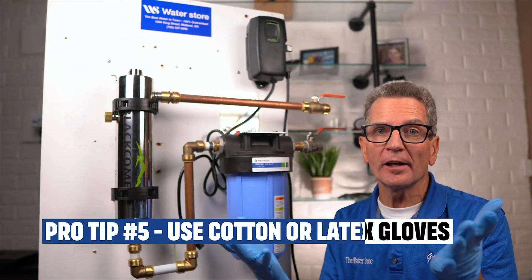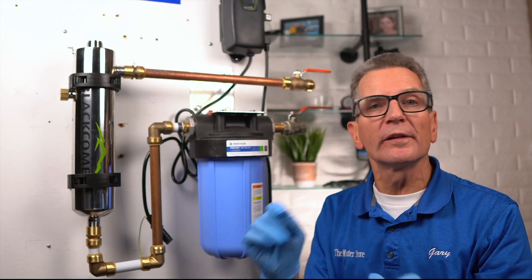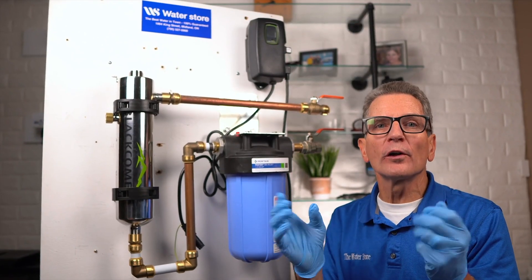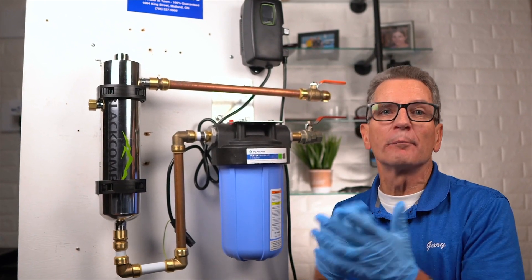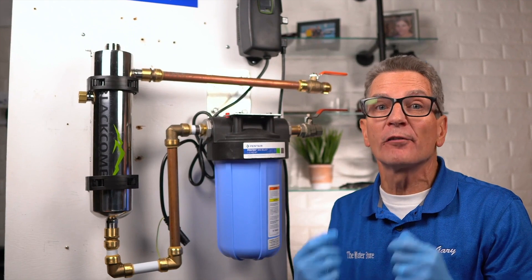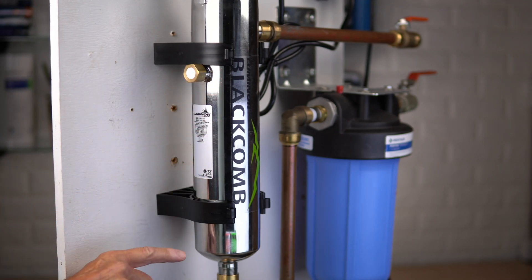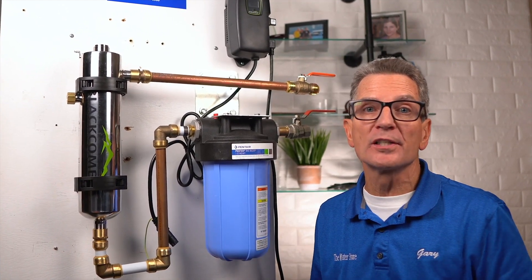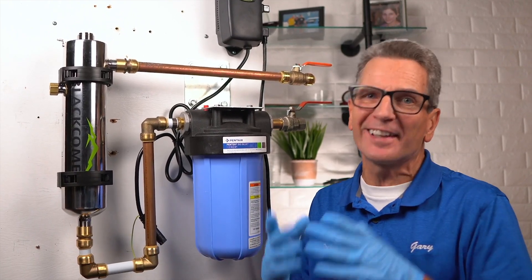Pro tip number five: the use of cotton or latex gloves is definitely recommended whenever you're handling anything to do with the quartz sleeve or the ultraviolet disinfection lamp itself. It protects the oils from your hands from being deposited on the quartz sleeve and compromising its performance, which could ultimately block the UV light from getting to the water. Pro tip number six: be careful that you're installing the Blackcomb version of these UV systems. Stay away from the proprietary systems from companies like Culligan, Water Depot, and Nelson, because you can only get replacement UV lamps from them and they can charge whatever they want.